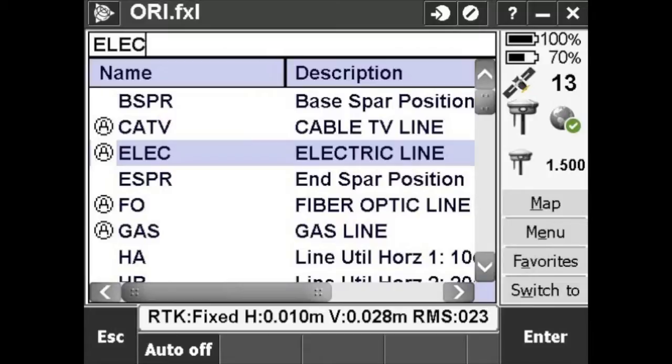Now let's measure the electric line, which we know runs along the side of the gas line. Remember to configure the transmitter to the new line, and change any frequency settings if necessary. Then go back to page 3 of the line panel, and input the code for Electric Line into the Utility AutoMesh feature.